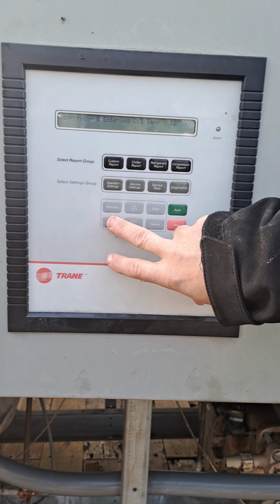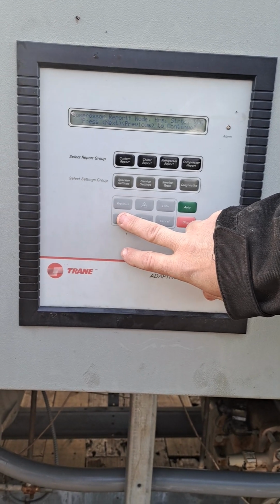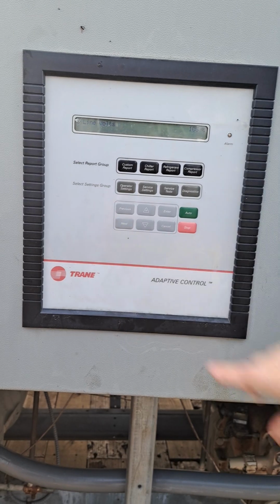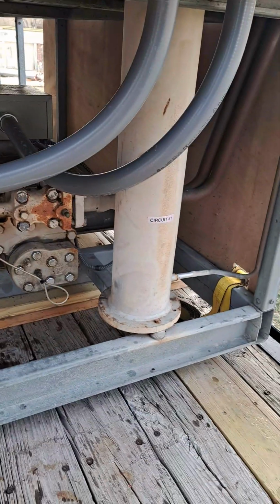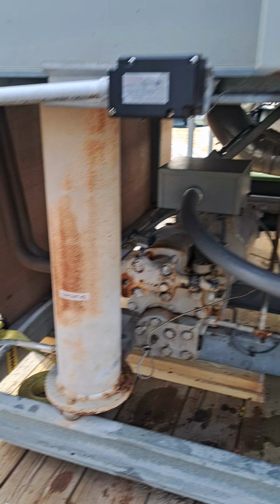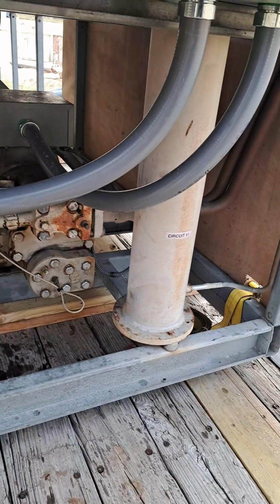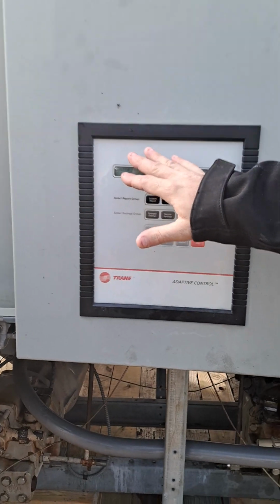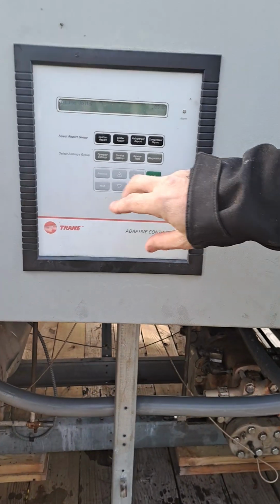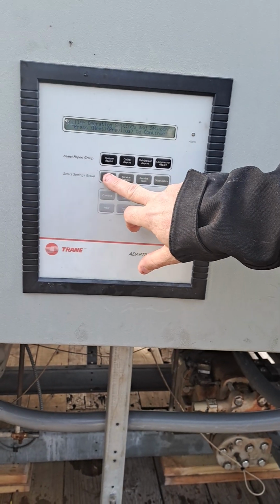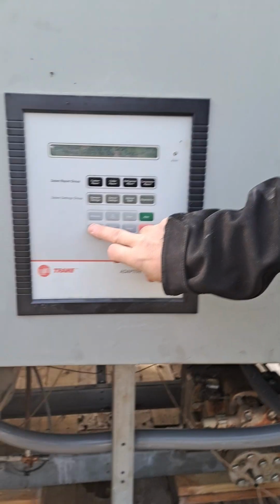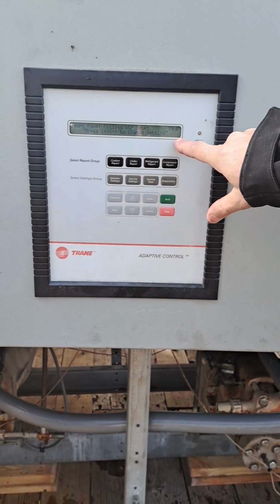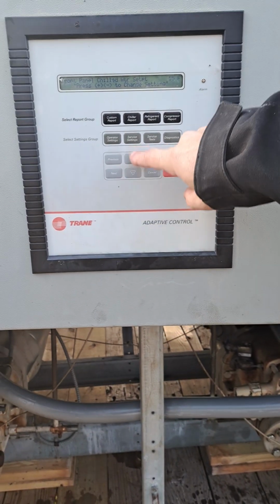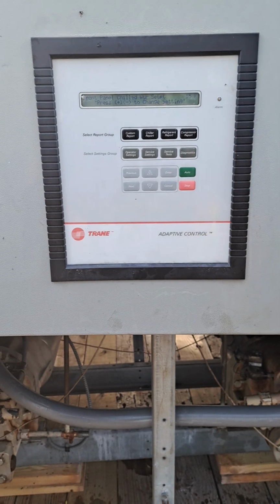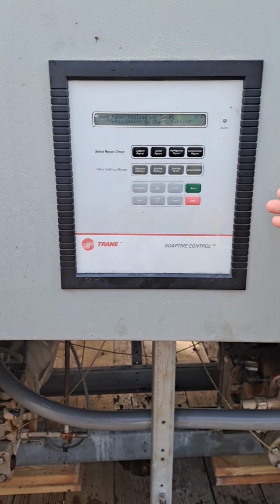And then if it keeps scrolling, it goes through your B side. So this is your A circuit, circuit 1, circuit 2 is your B circuit. Okay, so circuit 1 is A, circuit 2 is B circuits. Yeah, they're listed as A and B in here. Okay. 1 and 2. So you have your operator settings here. If you have to change your chilled water set point, that's right there. So you just press up and down and hit enter and it'll save it. Okay. So if you need to adjust that, you can.